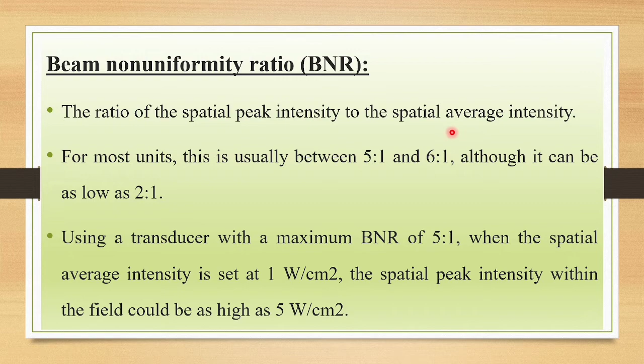Using a transducer with a maximum beam non-uniformity ratio of 6:1, when the spatial average intensity is set at 1.5 watts per centimeter square, the spatial peak intensity within the field could be as high as 9 watts per centimeter square. So with the 6:1 ratio, you can see 1.5 times 6 is equal to 9 watts per centimeter square. The next parameter is your spatial average intensity.